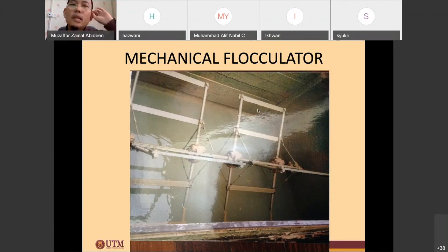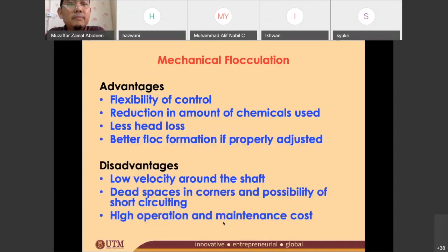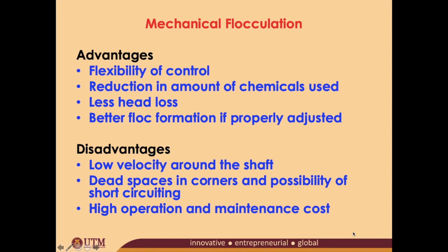These are the advantages of the mechanical flocculator. Flexibility and control is quite straightforward. There is a reduction in the amount of chemical used — when you have flexibility you can always reduce chemical use. The next advantage is less head loss. Compared to the hydraulic flocculator, which has greater head loss due to friction between the water and the baffles, the mechanical flocculator performs better. With flexibility in control you can also control the amount of chemicals, allowing you to form better flocs.